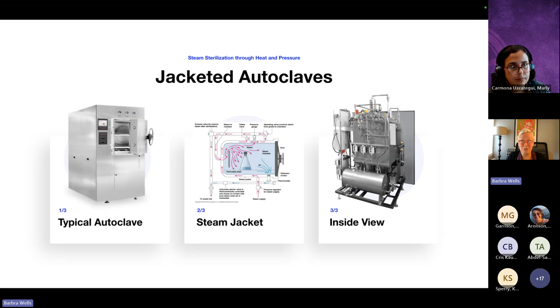When an autoclave is on or in standby mode, the jacket fills with steam to maintain a steady temperature all the time. Ta-da! But here's the clincher. Most autoclaves are designed to be on or in standby mode all the time. They're always hot and ready, so they're always drawing water and electricity. It's a lot of water.